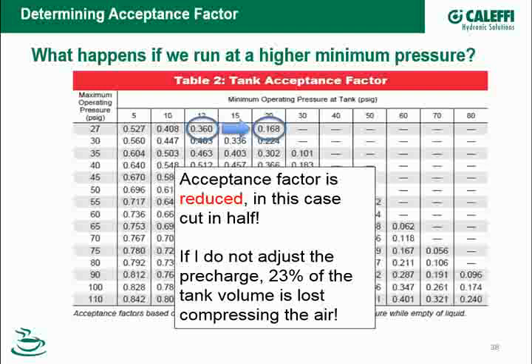So one of the concerns is if you're going to run at a higher pressure, just beware that you are running at a reduced acceptance factor. You're going to be able to use less of that tank's volume storing that water. So, typically at a higher pressure, the tank's volume has to get larger. The other thing that always concerns me when I listen to these discussions is when they're going from 12 psi to 18 or 20, are they adjusting the precharge, or are they just bumping the pressure up by increasing water, putting more water in the system?